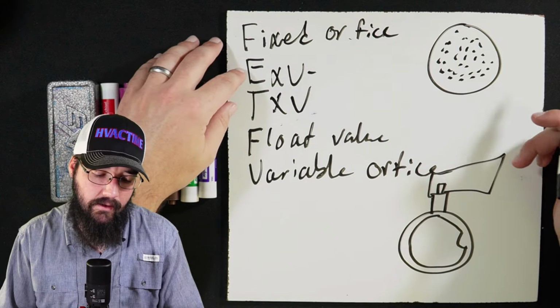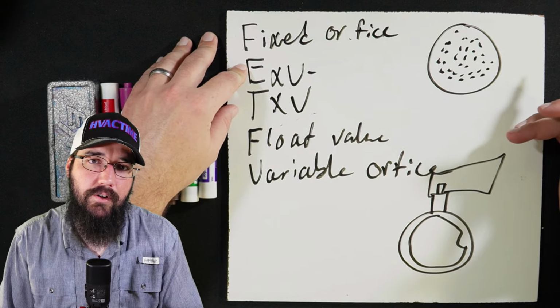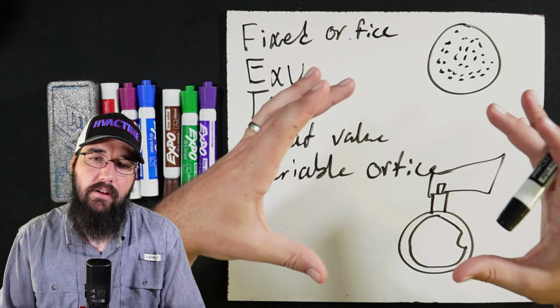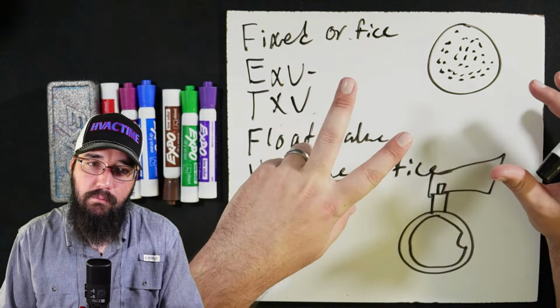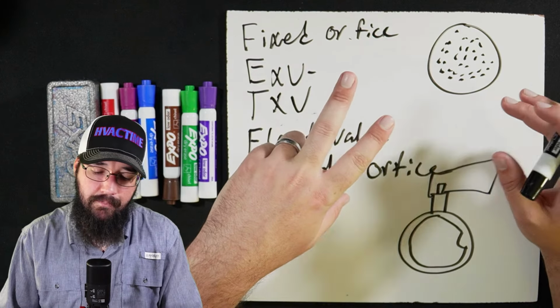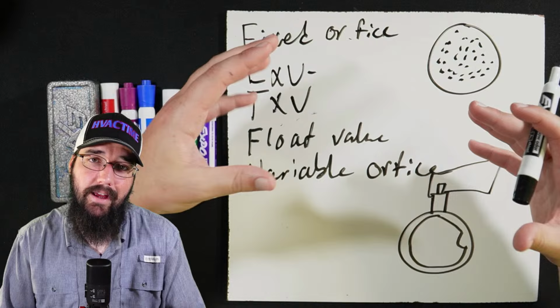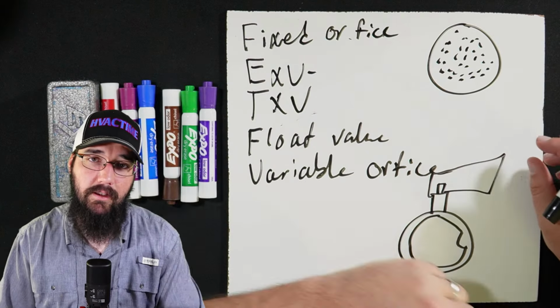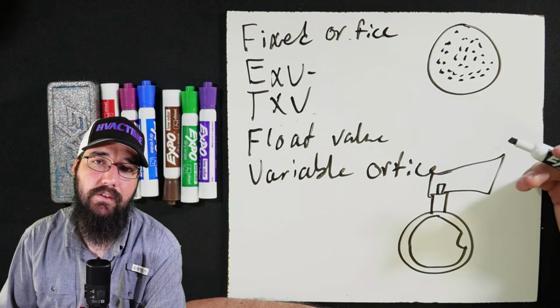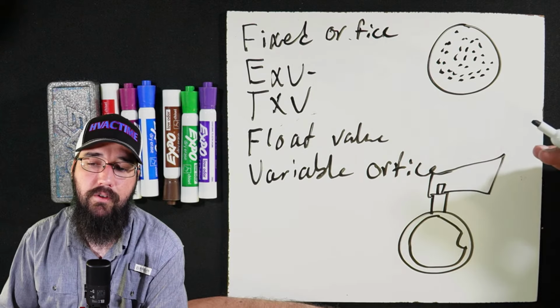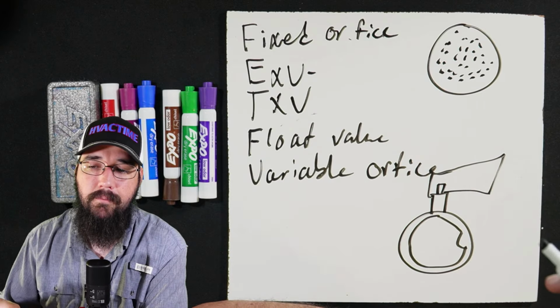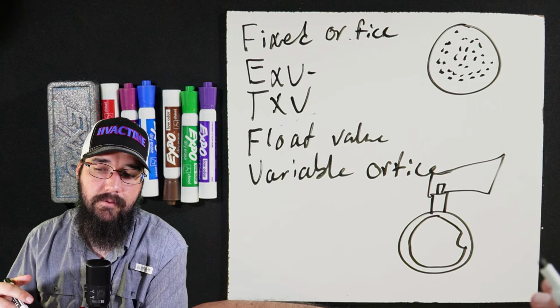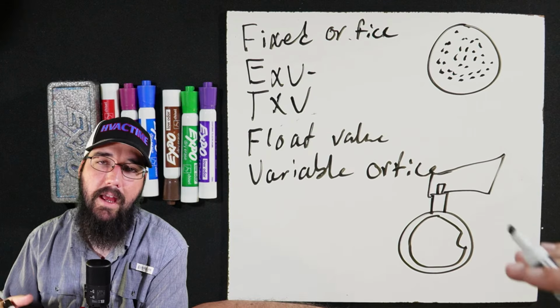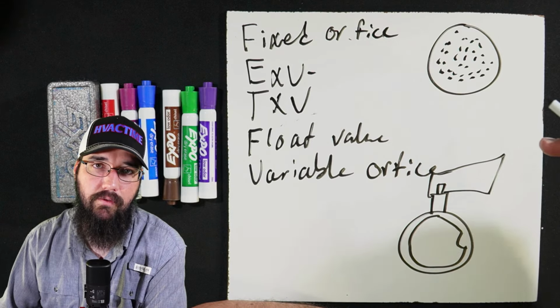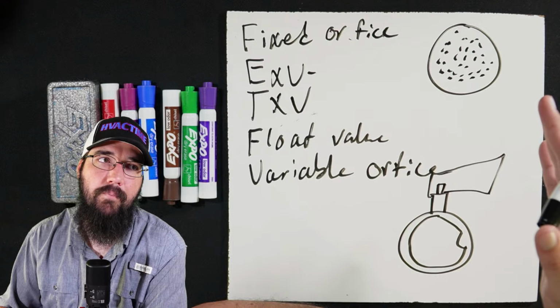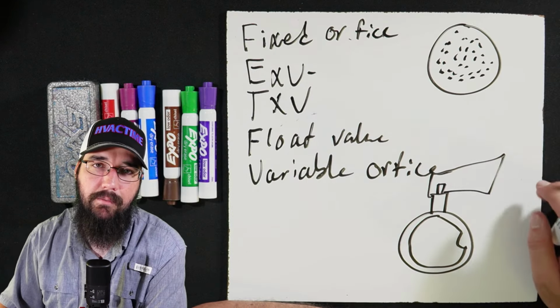That's also why you'll see a 300-ton RTHD, for example, have a metering EXV block with multiple heads in it, so that we can split the flow between the two heads to keep up without having this just ridiculously massive and expensive valve attached. Daikin does some of the same things, where as they get to some of their larger machines, they have multiple EXV heads involved, right? They're splitting the capacity, and we did the same things with TXVs as well.